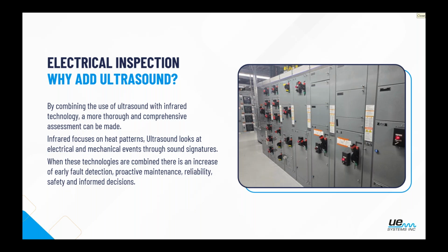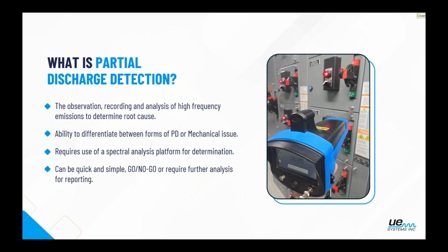And that's where typically we start recommending ultrasound use. Being able to hear what is happening inside that cabinet before we open that panel and allow any sort of event to possibly happen that would make us have a very bad day after that. So the beginning point is the safety aspect. And I'll have some examples of that coming up.